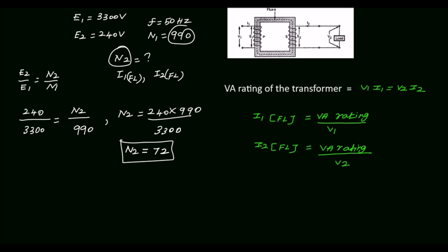Next, we will calculate the primary and secondary full load current. Normally the transformer rating is expressed in VA (volt-ampere). The VA rating of the transformer is the same on both the primary and secondary side. On the primary side, VA rating equals V1 times I1. On the secondary side, VA rating equals V2 times I2, where V1 is the primary terminal voltage, I1 is the primary full load current, V2 is the secondary terminal voltage, and I2 is the secondary full load current.